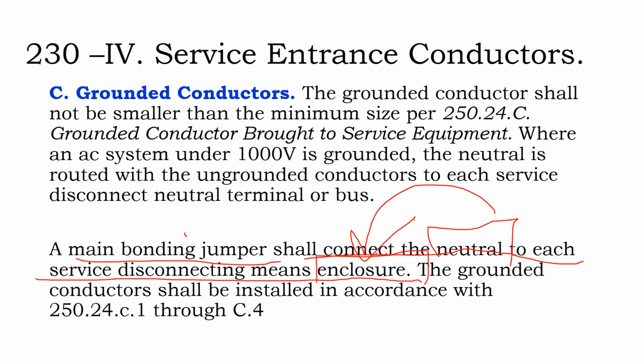You don't want that metal case to have high voltage on it, and then someone goes and touches it, and if they have low enough resistance, they're now the ground path. We want to avoid that. We want to have an effective ground path that connects these metal devices to ground.